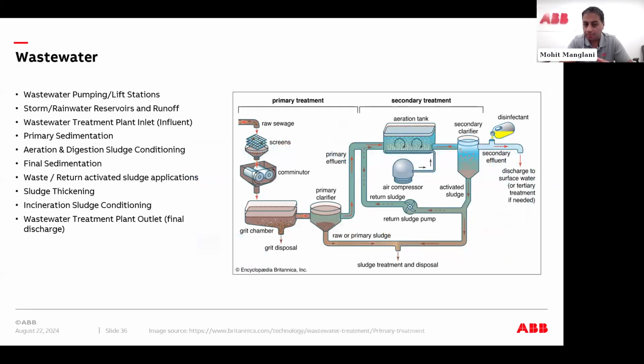On the wastewater side, again, all these are applications where mag meters can measure, outside the air compressor, obviously. RAS, WAS, grit disposal, bar screens, if you're having raw sewage come through, aeration tanks going in and out, secondary clarifiers, activated sludge, chemical dosing associated with the wastewater process, aeration, digestion, sludge conditioning. Again, the mag meter lives in all of these spaces. So again, the idea is that you want to make sure you apply best practices with any of the applications you might come across.